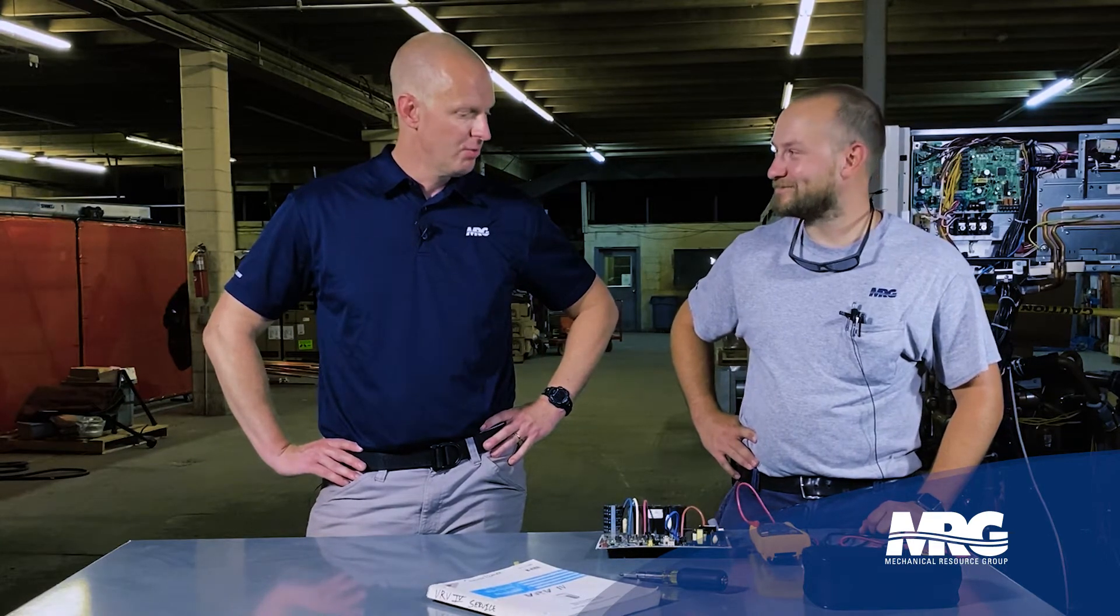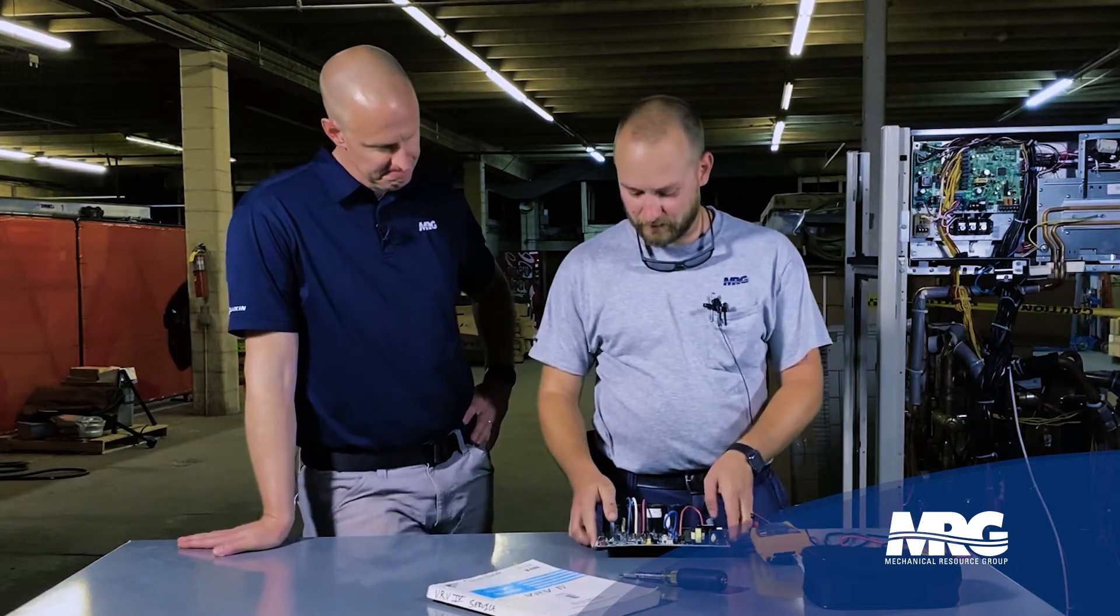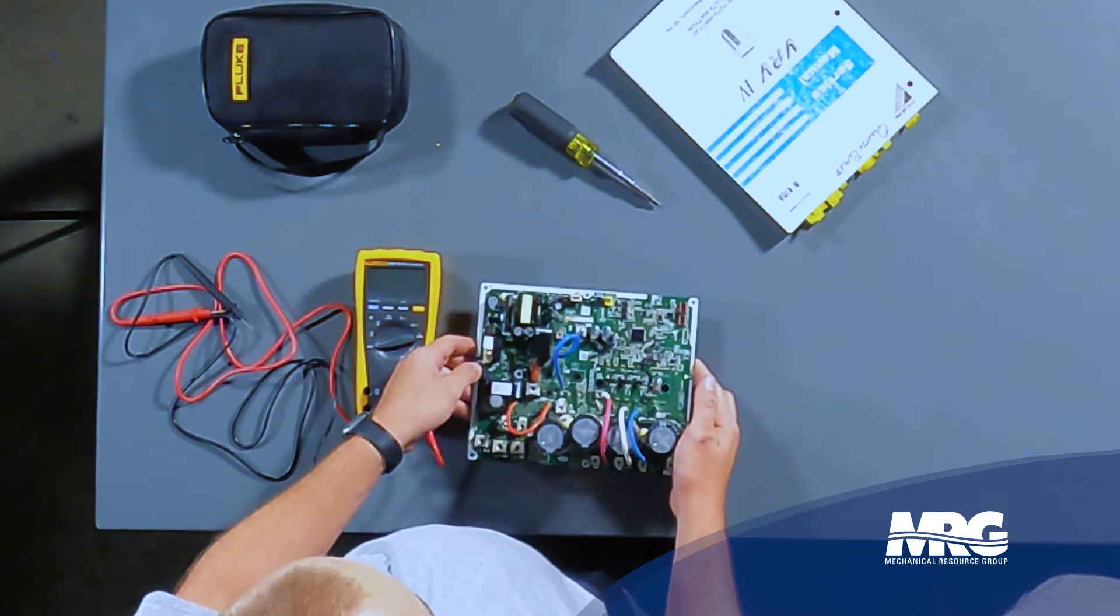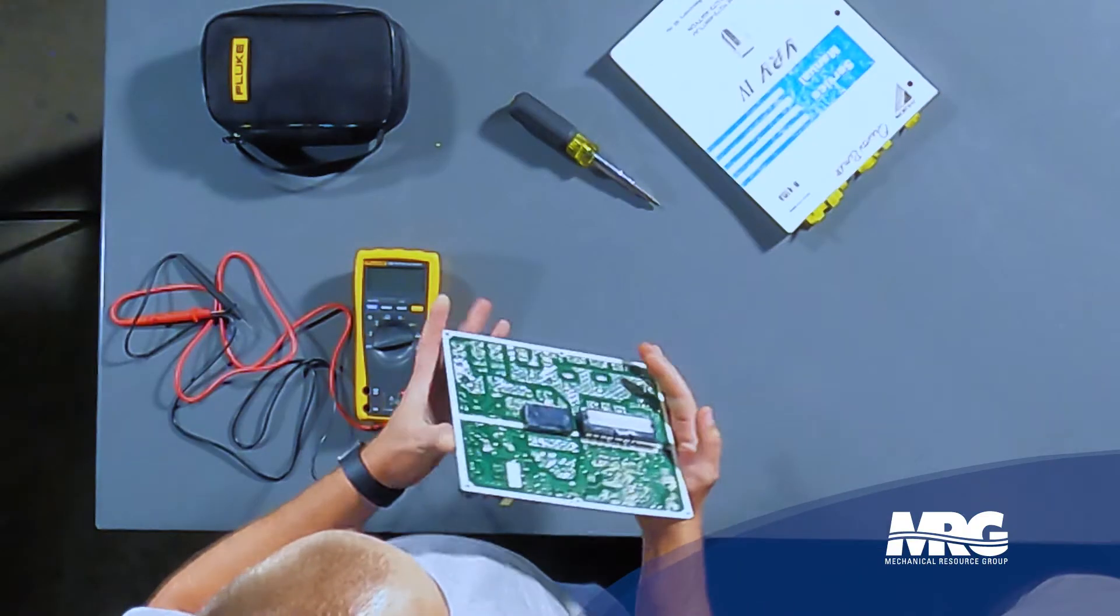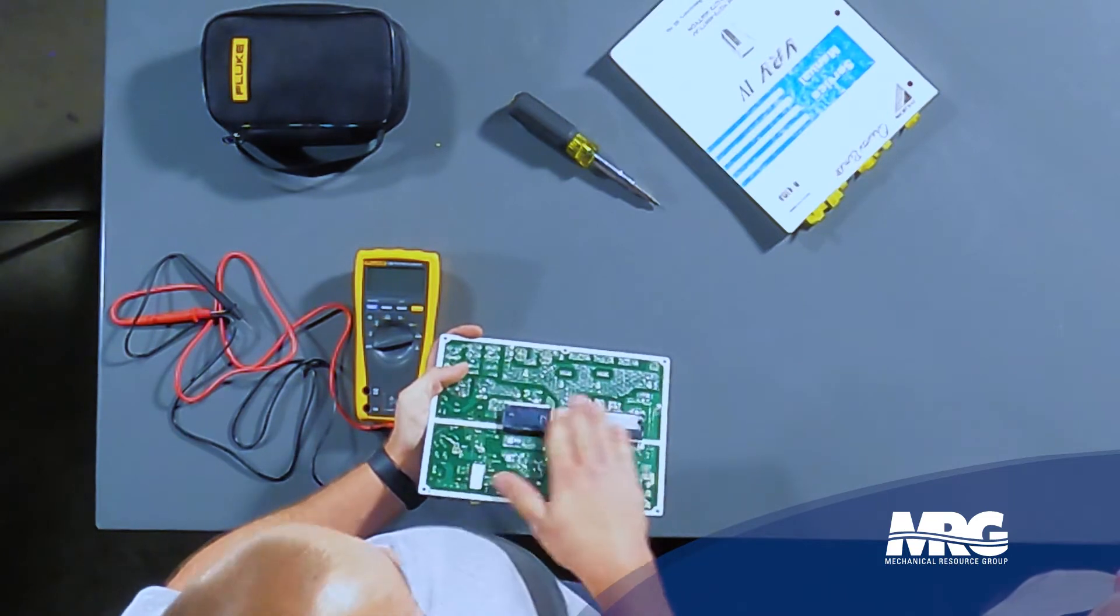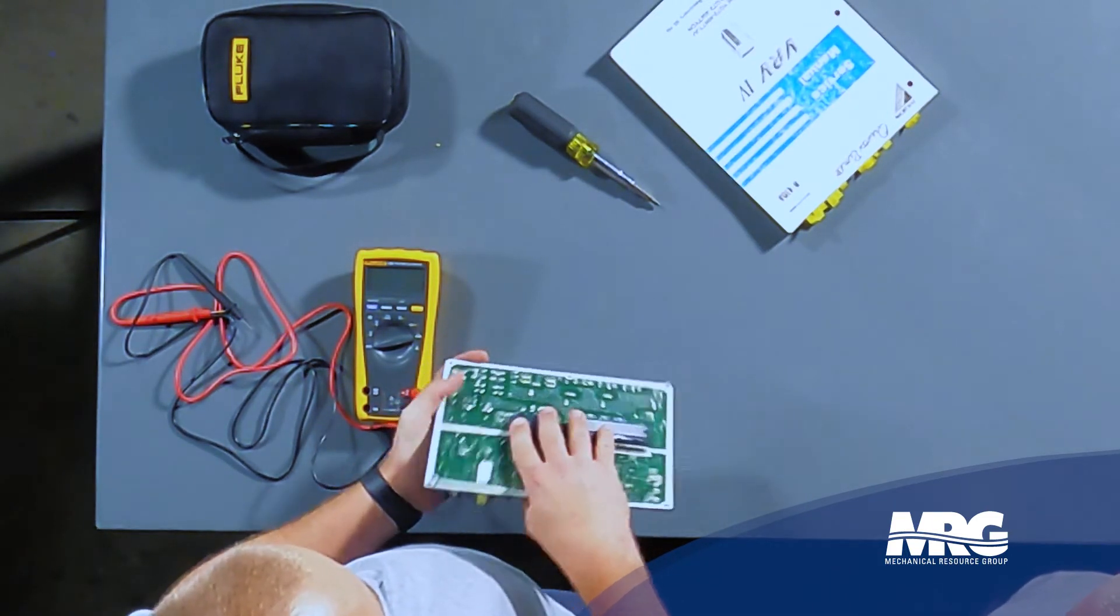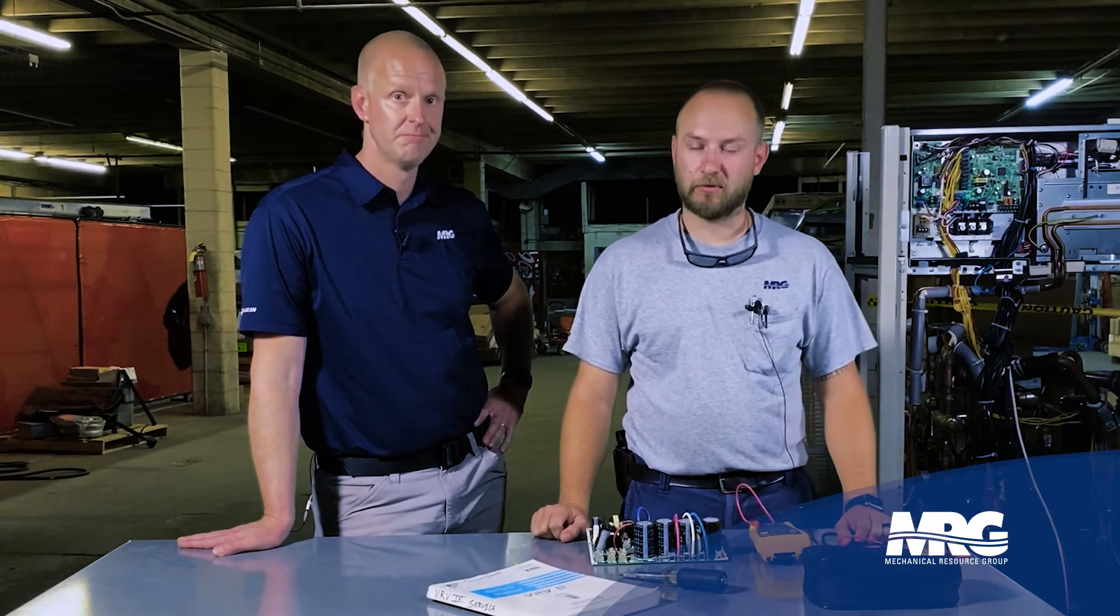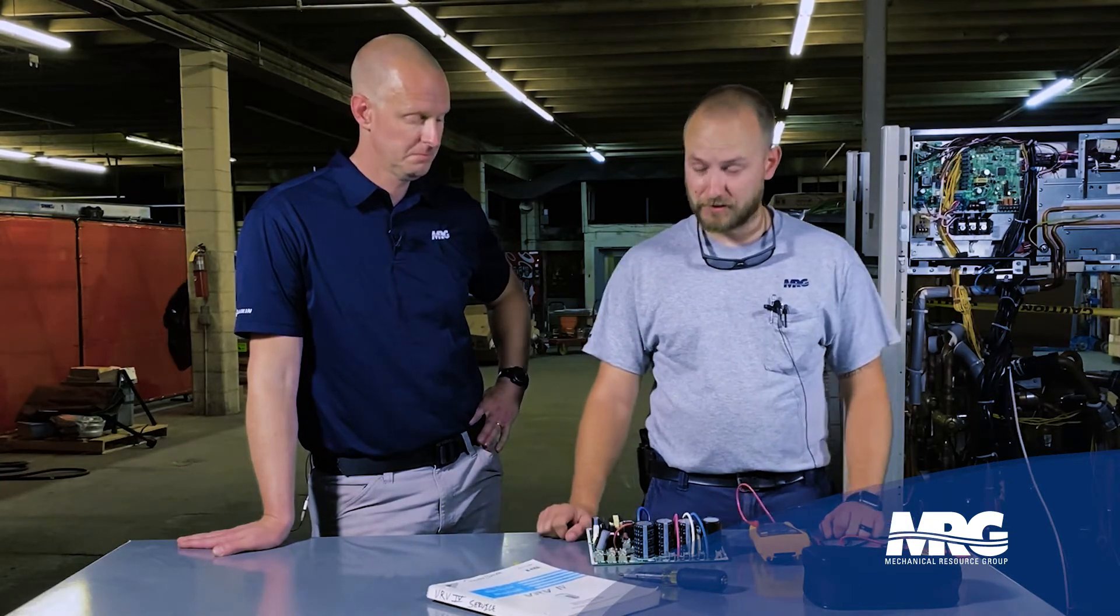Glad to be here. So what we've done here is we've taken an inverter board out of a Daikin VRV4. Naturally, this will normally be inside the VRV module. In one of the earlier videos, we talked about the heat sink on the back of the inverter board, which is cooled by the refrigerant circuit. But basically, we're going to talk about today how to test out the diode bridge on this inverter board. We put it here on the bench for simplicity's sake, but let's get into it.